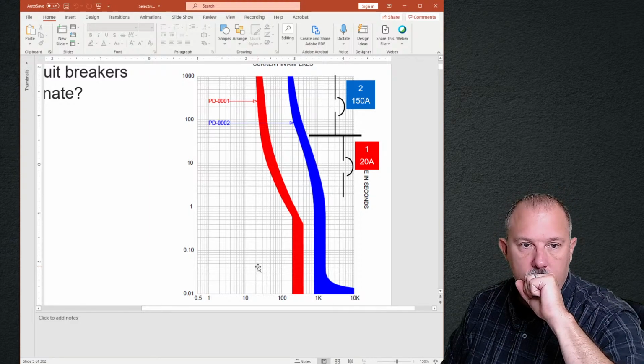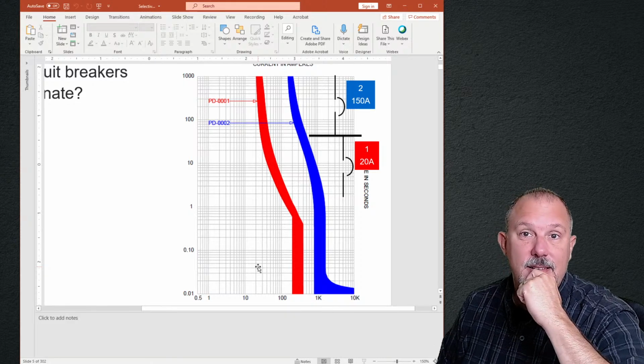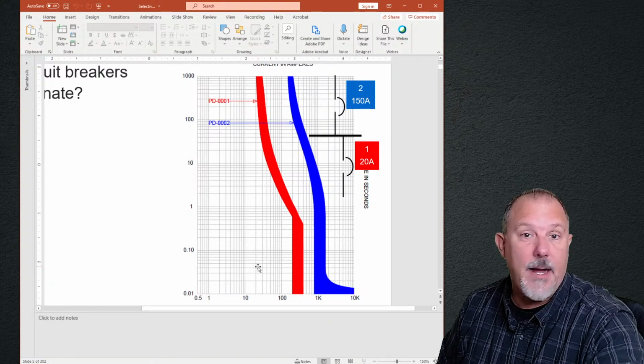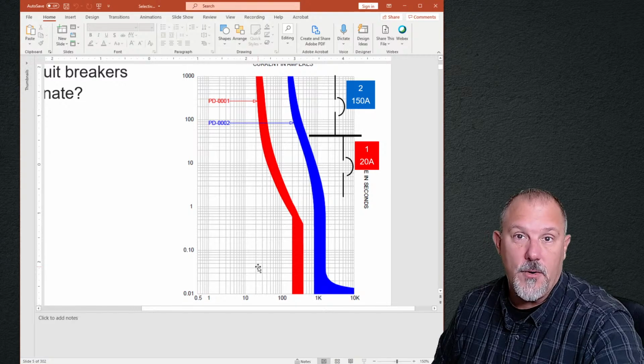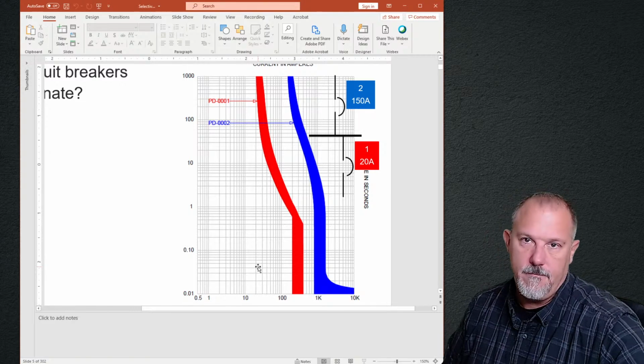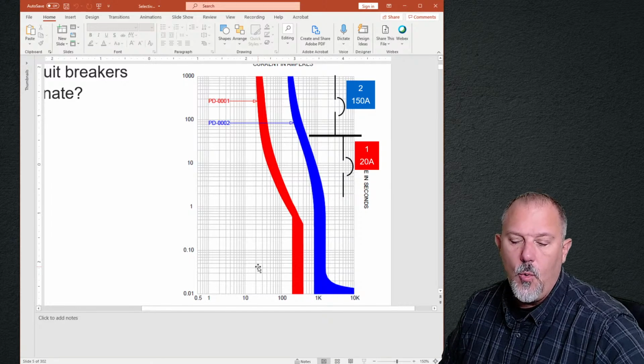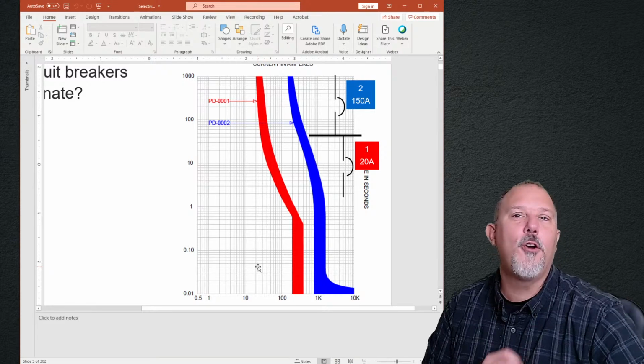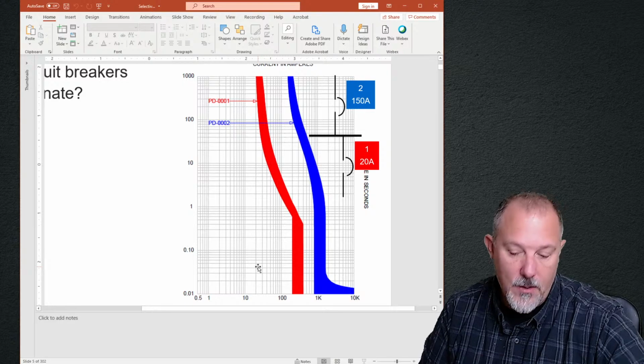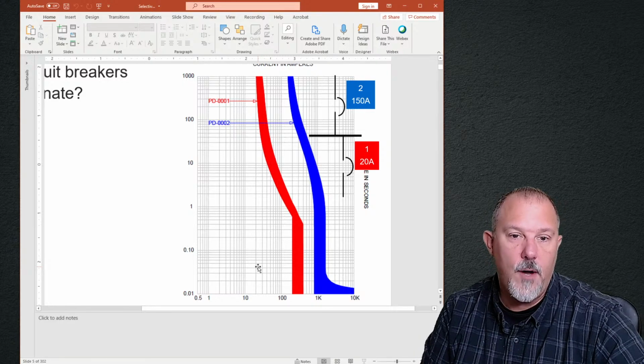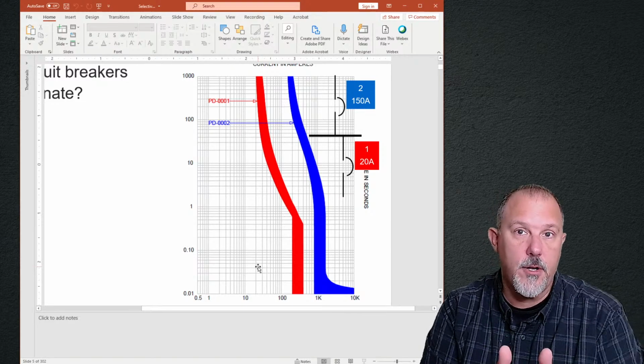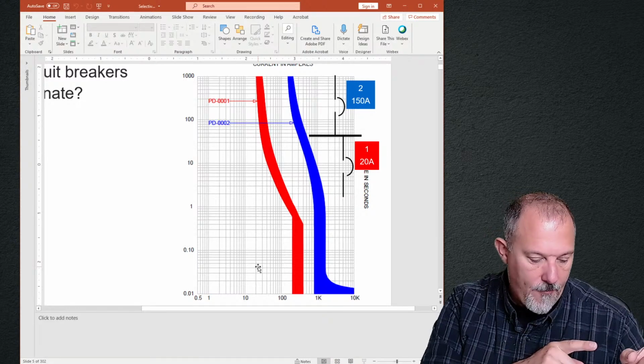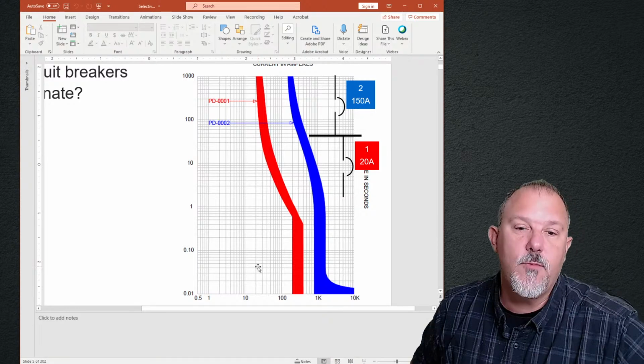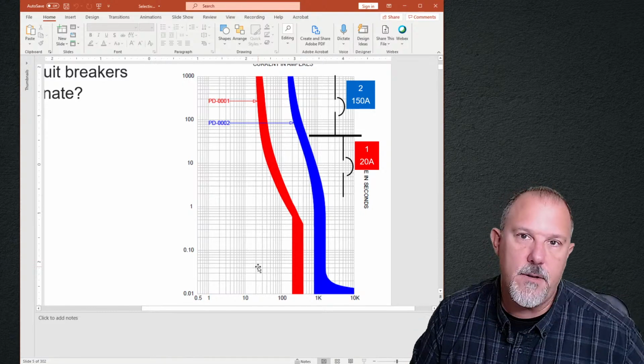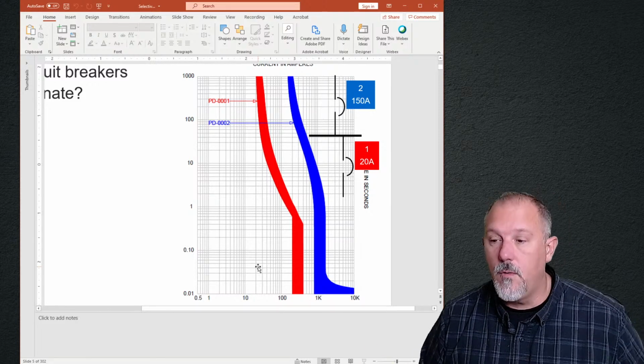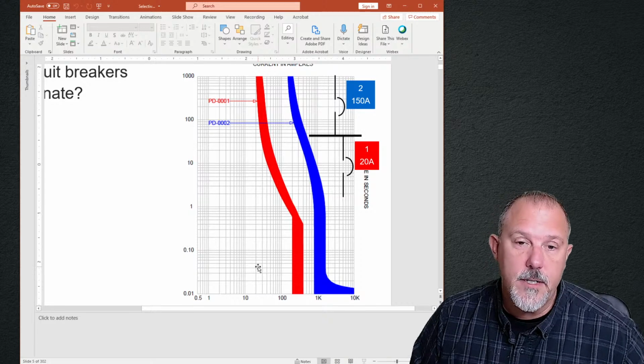And I said, what's the fault current? Four-word sentence. When I emailed it, I responded back and said, what's the fault current? And that individual called me. And it was a she. And she said, what do you mean, what's the fault current? In an argumentative fashion. And I said, well, I can't answer the question of selective coordination without knowing the fault current. So think about the definition we just read. And what she said, in a frustrated manner, was 10,000 amps. And I went, oh, okay. 10,000 amps, then they don't selectively coordinate.